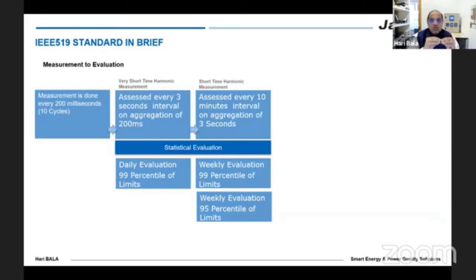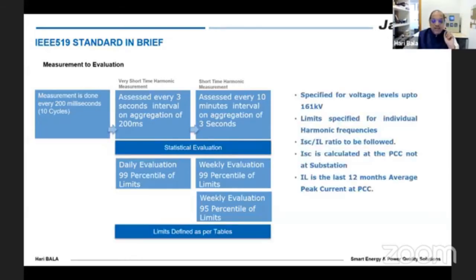Why have they given these three kinds of evaluation? Because different load conditions can have different kinds of harmonic injection. For example, a foundry plant can have very high changes within the 3 seconds, but their limits are very high for 99 percentile limits on daily values. Whereas a textile mill, for example, can have more or less steady values, where we can evaluate for 95 or 99 percentile on a weekly basis. So this is just an evaluation technique. There are three evaluation techniques given for harmonics, as per the defined tables.